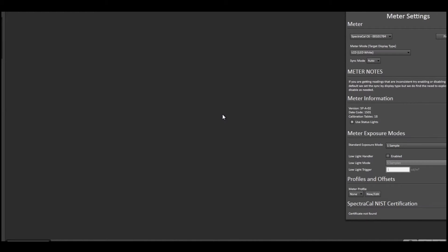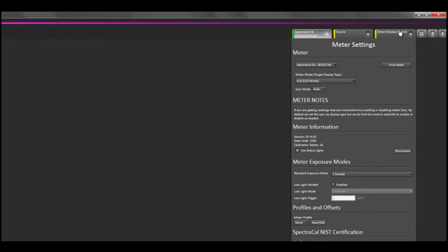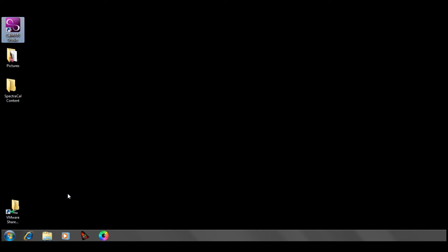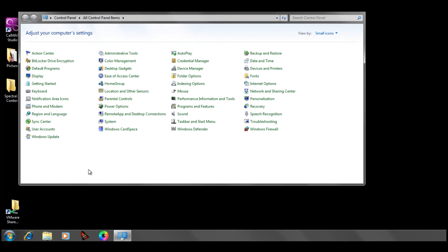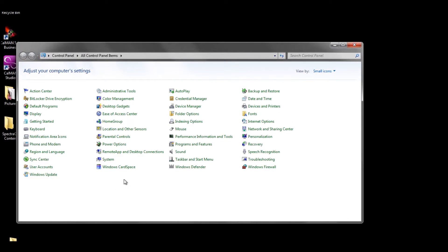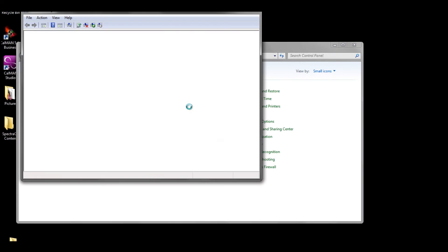If for some reason CalMAN isn't able to connect to the meter, go ahead and close down CalMAN, navigate to the Windows Start button, open Control Panel, then Device Manager.